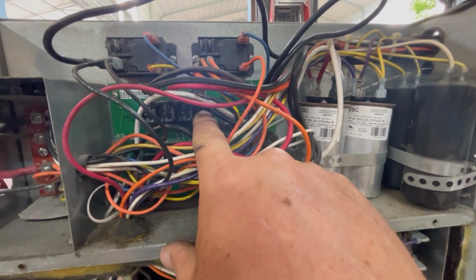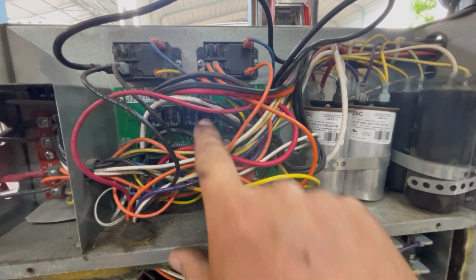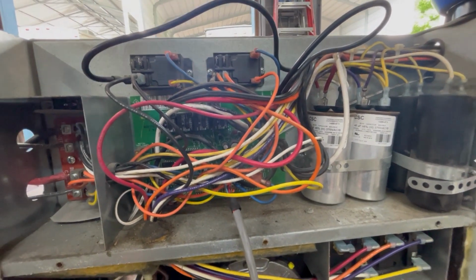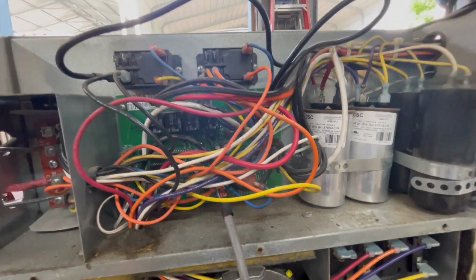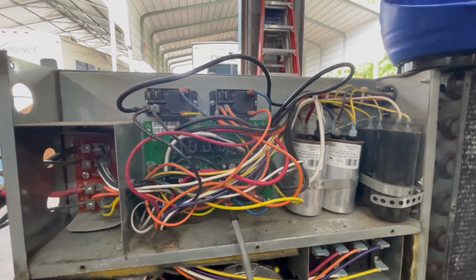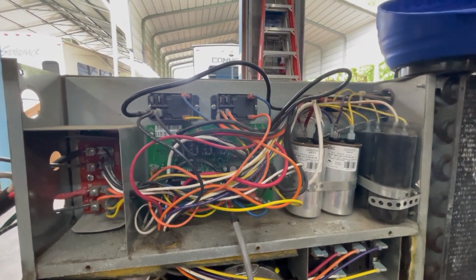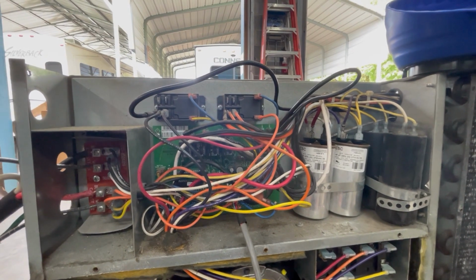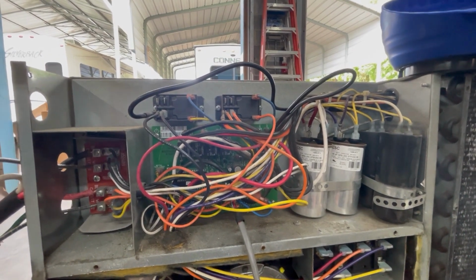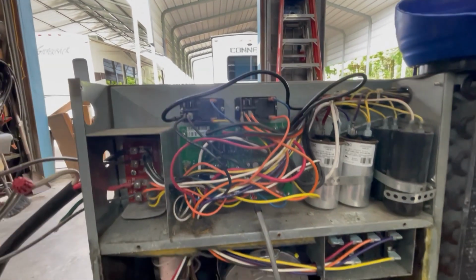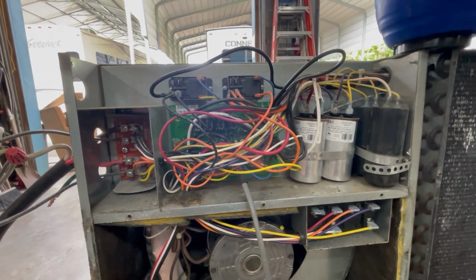The relay on this control board is just cycling on and off, on and off. So what we're going to do is start with that board, because if we do have a bad compressor, which is what they're telling us is going on, we're going to have to start with that board first. Let's put our test board on there and see what happens.